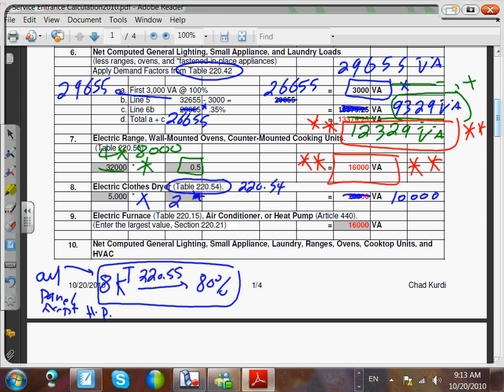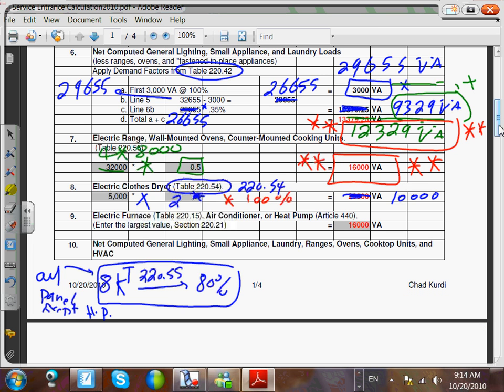Okay. So 2 times 10. Do I have to do it? What's my derating factor? And I want you guys to add a derating factor of 100%. So you remind yourself that the derating factor is 100%. Now I know this is for the main big fat panel. When it comes to the common panel, how many dryers do I have fed from the common panel? 2. Yes, Bill, my friend.